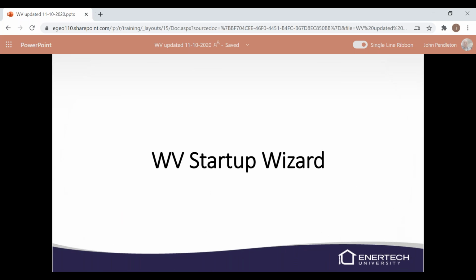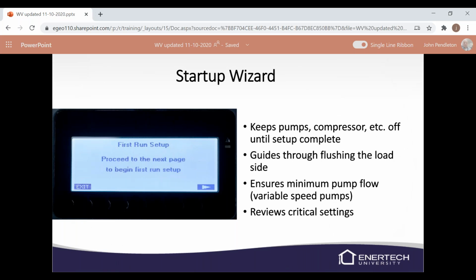So the startup wizard: when you first power up the unit after you've got it installed, it'll take you through the first run setup. It'll tell you right on the screen, first run setup. Do you want to start? And you can just press next. Here's actually the actual screen. It's going to keep the pumps and compressors all off until setup is complete, and it'll guide you through the flushing of the load, because again, we have to move that hot water valve to make sure we flushed the domestic hot water circuit.